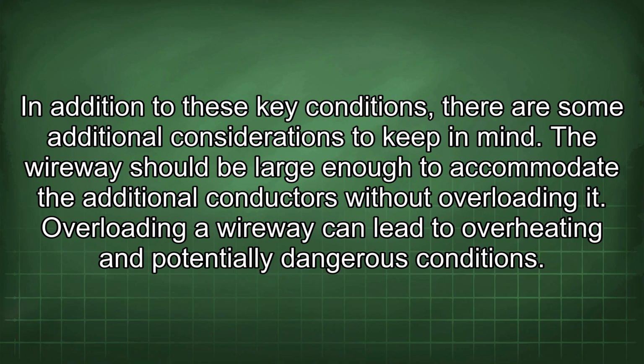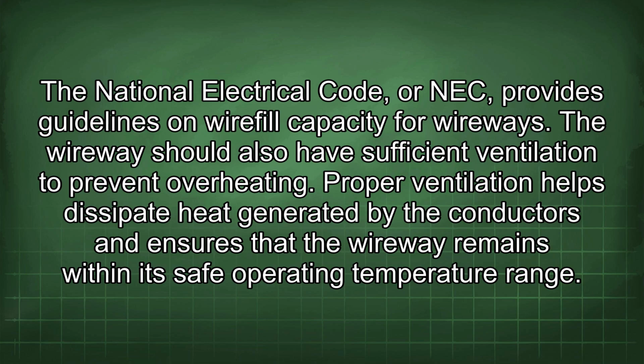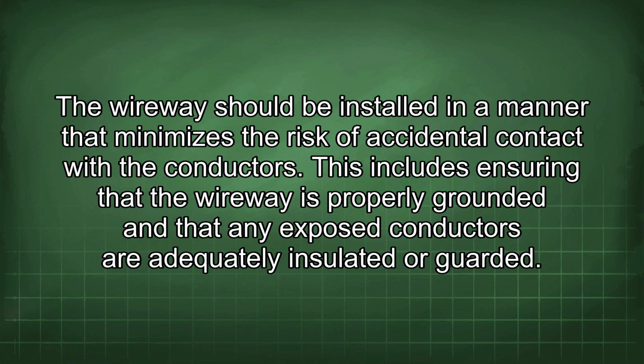In addition to these key conditions, there are some additional considerations to keep in mind. The wireway should be large enough to accommodate the additional conductors without overloading it. Overloading a wireway can lead to overheating and potentially dangerous conditions. The National Electrical Code, or NEC, provides guidelines on wireway capacity. The wireway should also have sufficient ventilation to prevent overheating. Proper ventilation helps dissipate heat generated by the conductors and ensures that the wireway remains within its safe operating temperature range. The wireway should be installed in a manner that minimizes the risk of accidental contact with the conductors. This includes ensuring that the wireway is properly grounded and that any exposed conductors are adequately insulated or guarded.